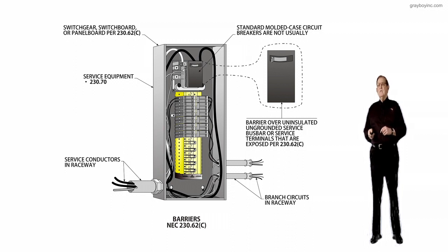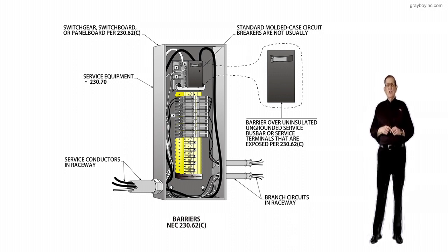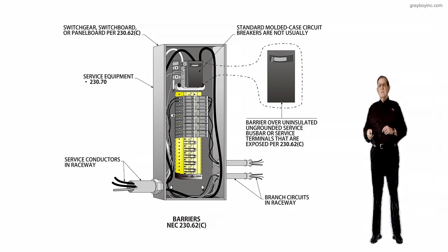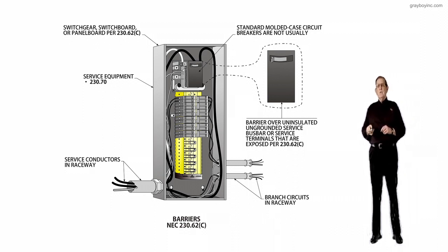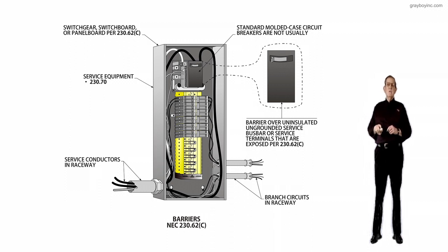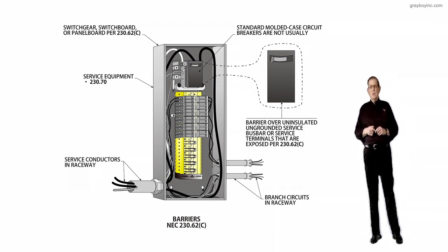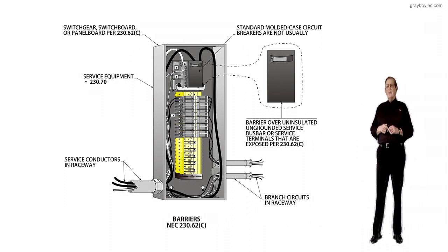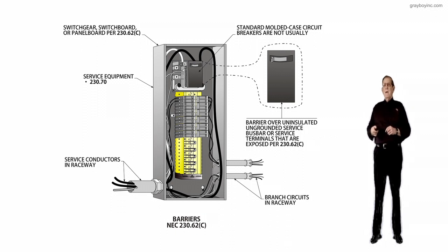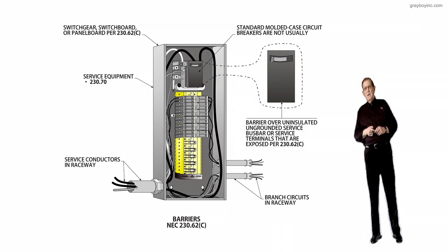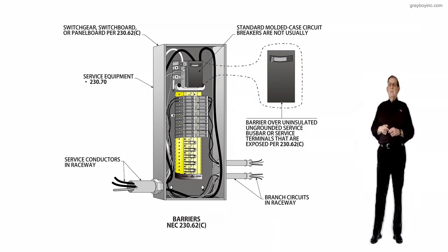The same hazard that initiated this change exists in all service equipment, including but not limited to enclosed circuit breakers, transfer switches marked suitable for use as service equipment, enclosed switches, motor control switches marked suitable for use as service equipment, industrial control panels installed in accordance with Article 409 and marked suitable for use as service equipment, and others that might be available to us.